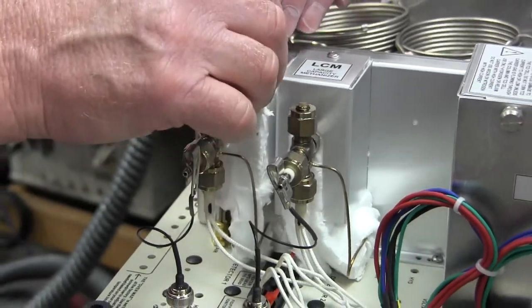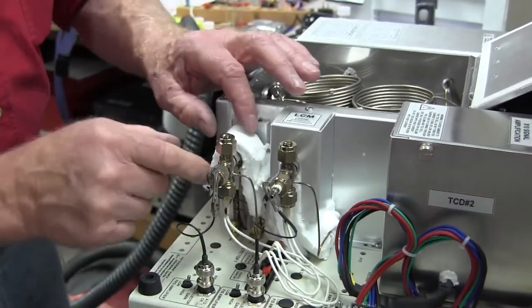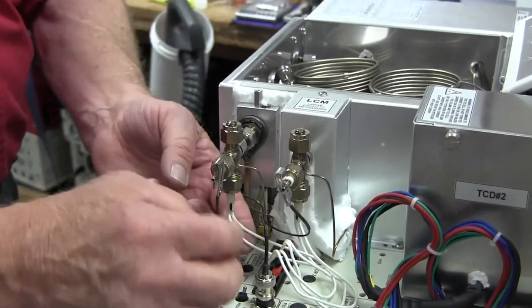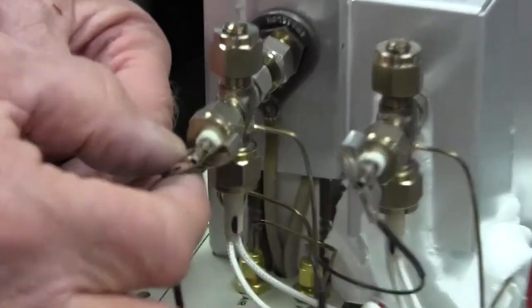Be gentle and try not to break the insulation, it kind of pills and fuzzes. Take the insulation off, try not to wreck it. This is the collector electrode of the FID.